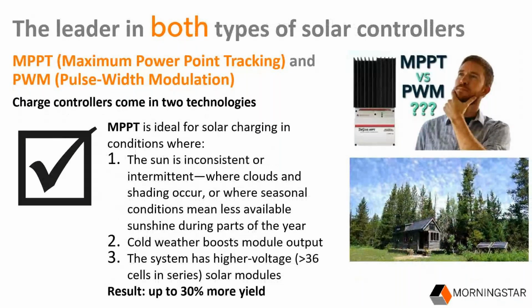MPPT controllers, on the other hand, operate at maximum power voltage, or VMP, which is higher than the battery voltage. The controller converts the incoming high VMP down to the battery voltage to charge the battery. And because they can step down the incoming high voltage, MPPT controllers have fewer module restrictions compared to PWMs.